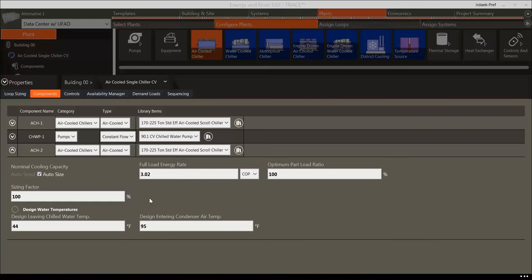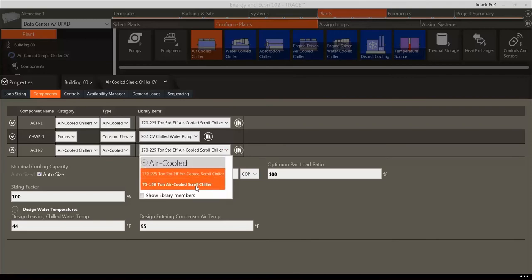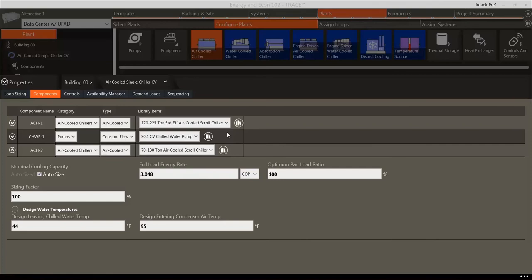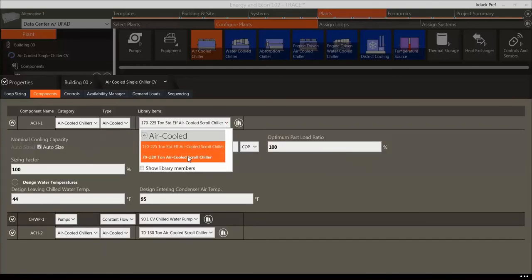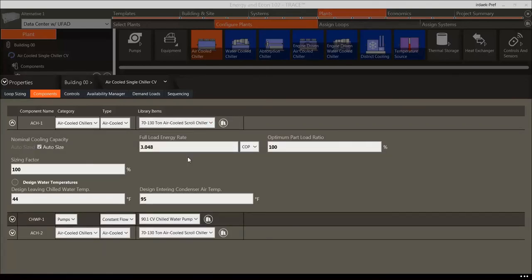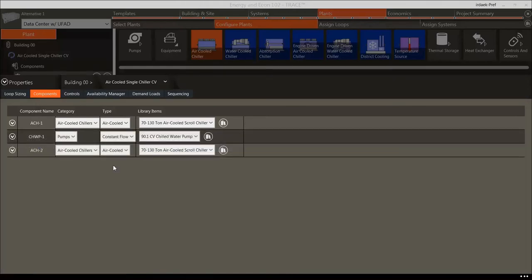When a chiller or piece of equipment is added to the Configure Plants diagram, it is automatically assigned a default library member with set performance characteristics. To edit the performance of the chiller, highlight it and open the Properties. On the Components tab, you can see the chiller's performance characteristics. Change the chiller to a 70 to 130 ton air-cooled scroll chiller — notice this changes all associated details, including the full load energy rate. The other sections available in Properties that impact loop sizing and control are Loop Sizing, Controls, Availability Manager, Demand Loads, and Sequencing.